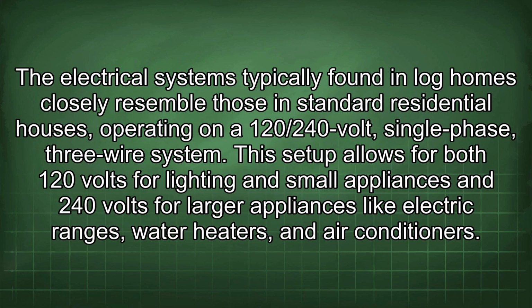The electrical systems typically found in log homes closely resemble those in standard residential houses, operating on a 120/240 volt, single-phase, 3-wire system. This setup allows for both 120 volts for lighting and small appliances and 240 volts for larger appliances like electric ranges, water heaters, and air conditioners.